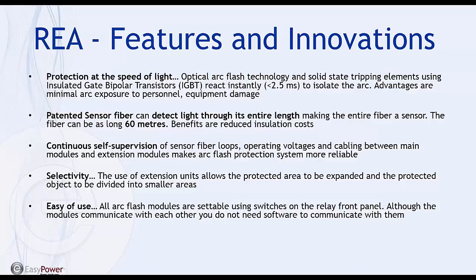And keep in mind, this is the detection of the light for the arc, and also the current, and then closing the contact and issuing a trip to the breaker. So it takes that amount of time to issue a trip to the breaker, which is negligible compared to the breaker time because it's so small. You have the loop sensors. They can sense light throughout their entire length, which can be as long as 60 meters. You have supervision for the sensors, which is very important. You also have supervision for all the different connections between the modules as well.